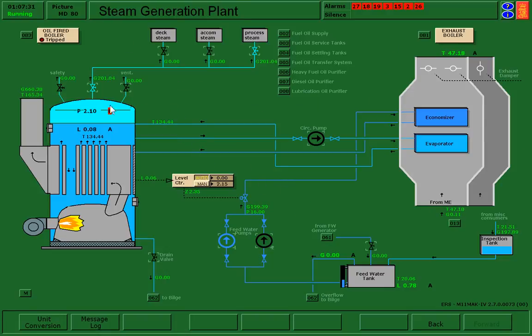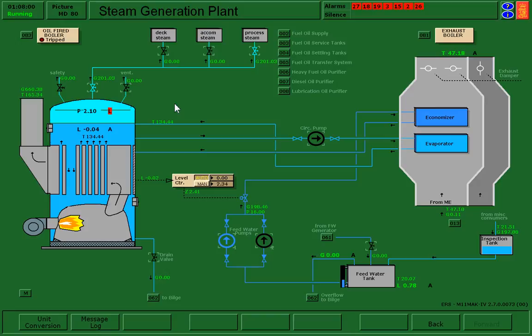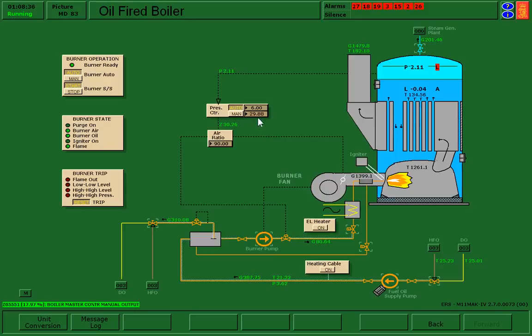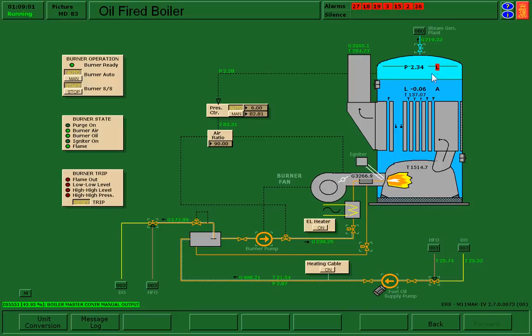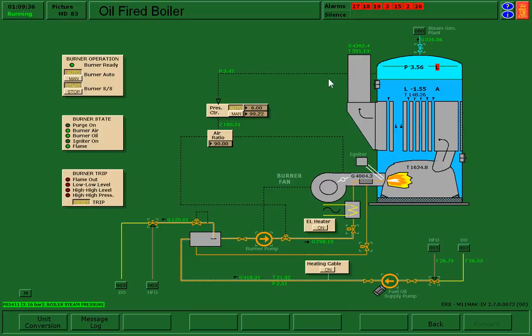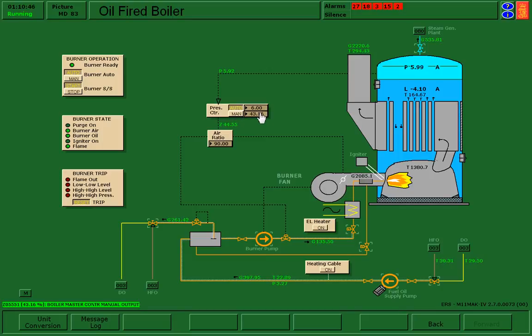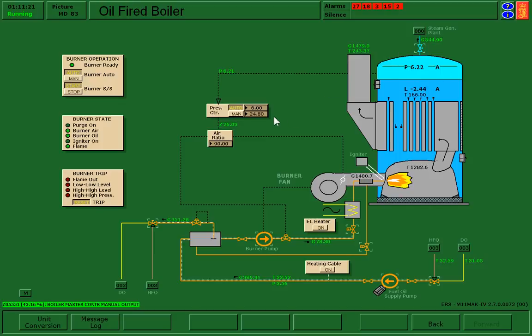One more thing that we're going to do now that we have our steam going off to process is return back to our burner page and we'll set our pressure controller over to auto. What this is going to do is it's going to adjust the firing rate of the boiler in order to bring our pressure up to our desired pressure of six bar. For our scenario, what we want to get to is auto and auto at the end. In real life, we would likely manually adjust our pressure controller so that we would bring that pressure up manually, still trying to do it at a slow rate, and then once we got close, switch it over into an auto firing mode.